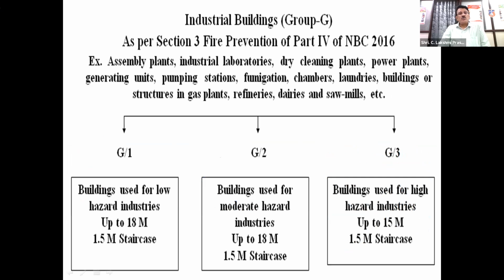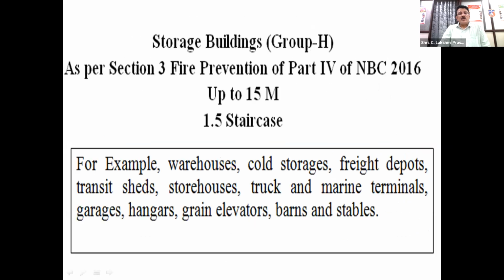Then we have got storage buildings. Then industrial buildings, they have low hazard, moderate hazard, and high hazard industrial buildings, G1, G2, and G3. Then we have got storage buildings, where the height is capped at 15 meters. A storage building is not supposed to be more than 15 meters because of the heavy fire load that it contains, and the warehouses and cold storages, freight depots, transit sheds, all these come under this. Even truck and marine terminals, garages, hangars, grain elevators, barns and stables, all these come under storage.